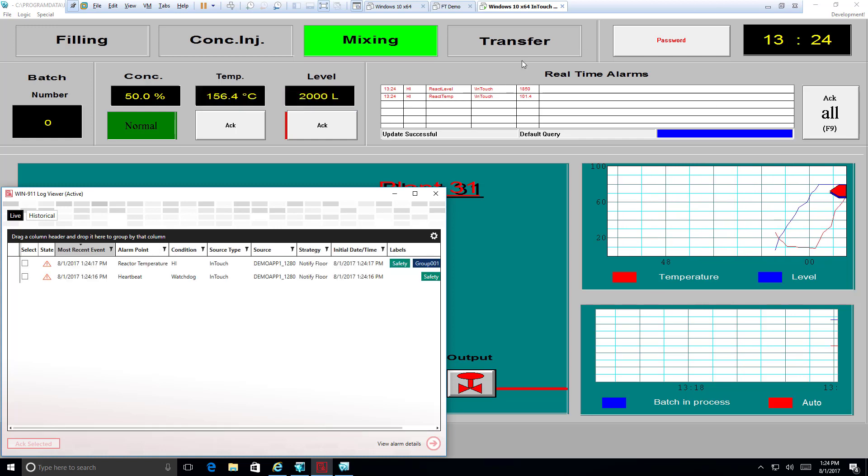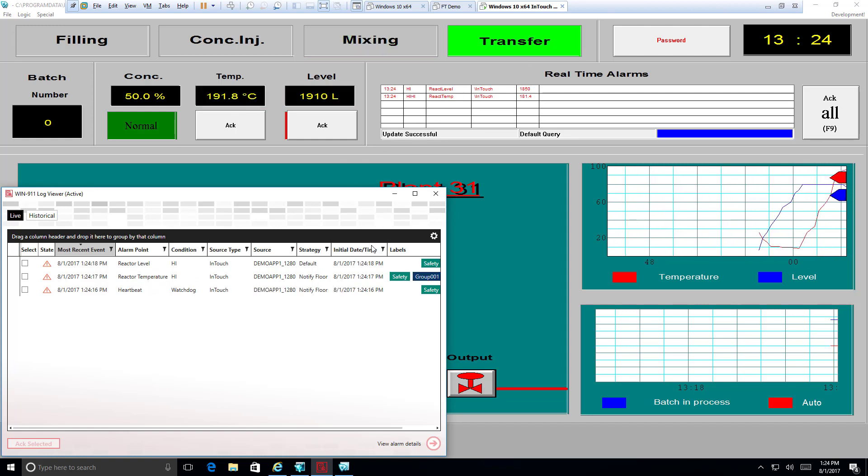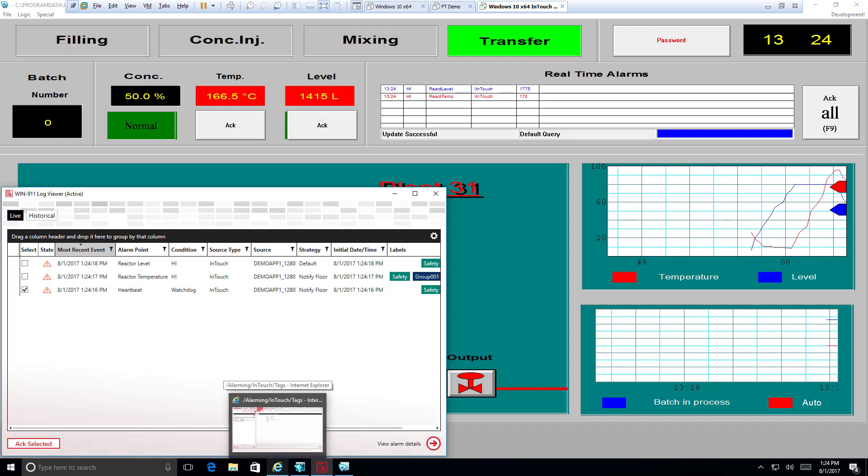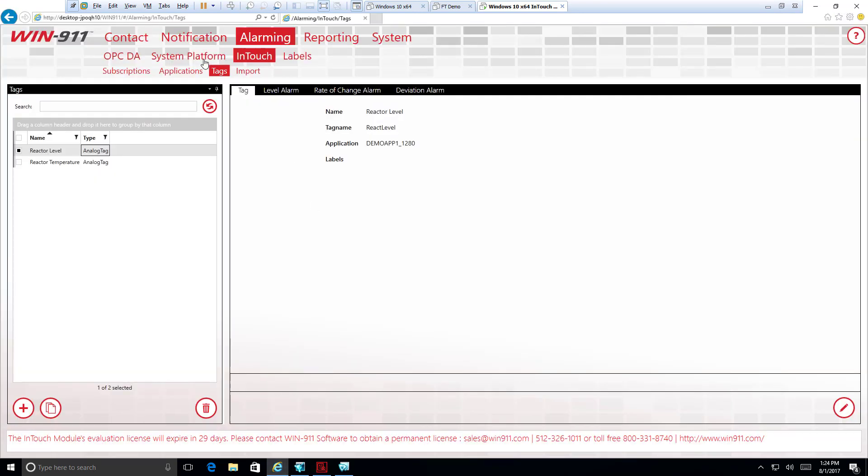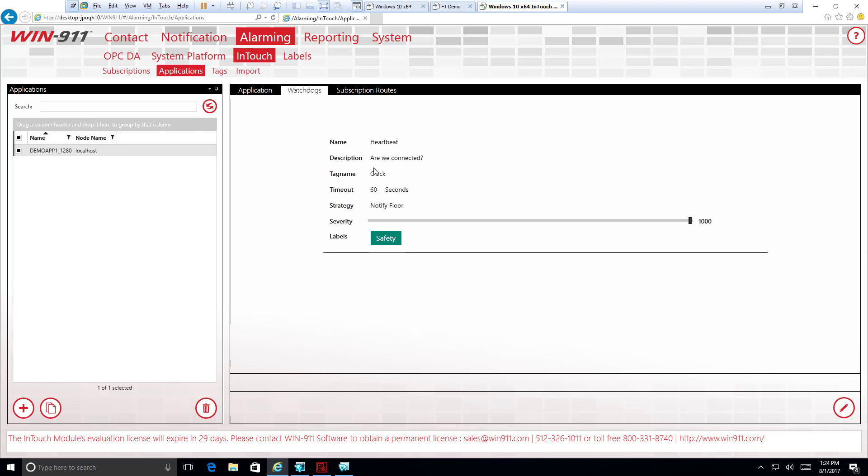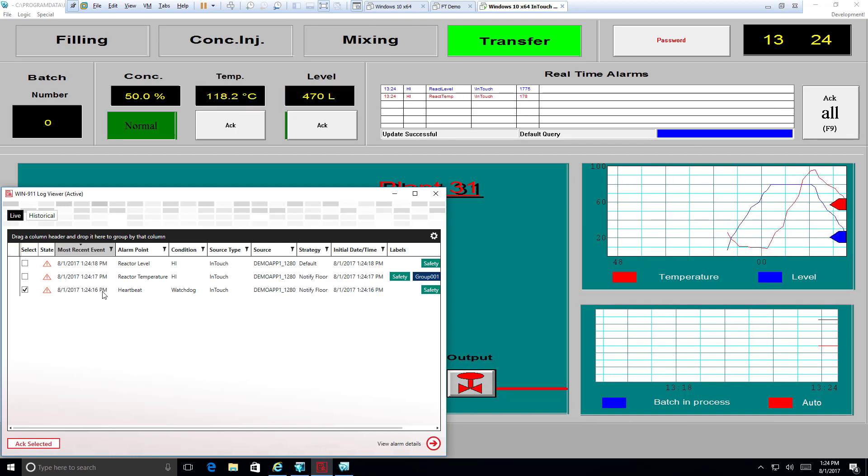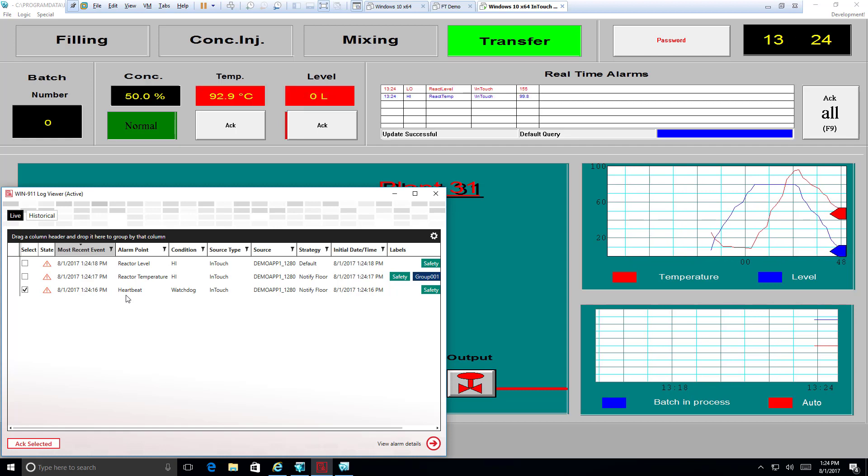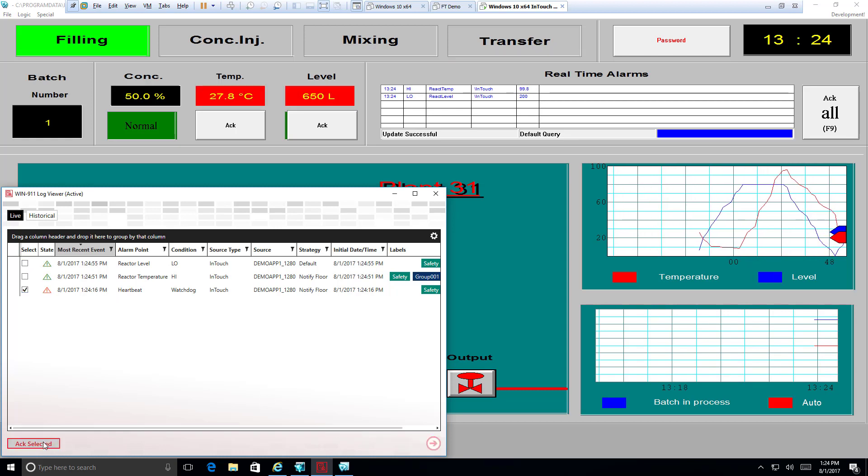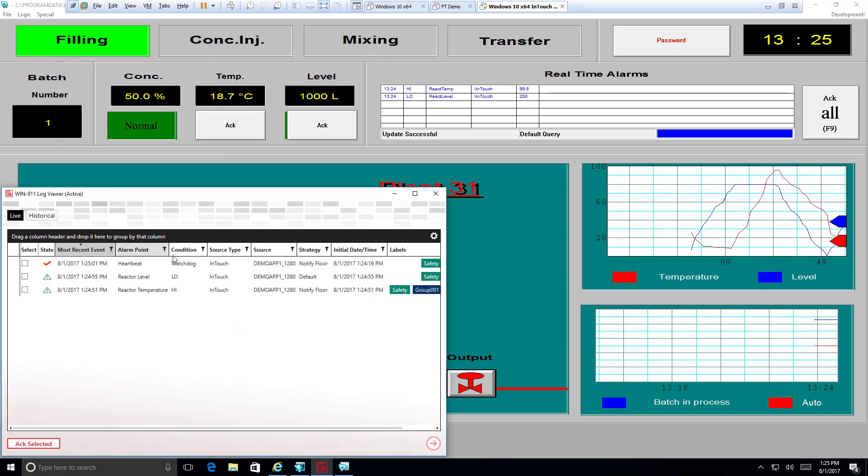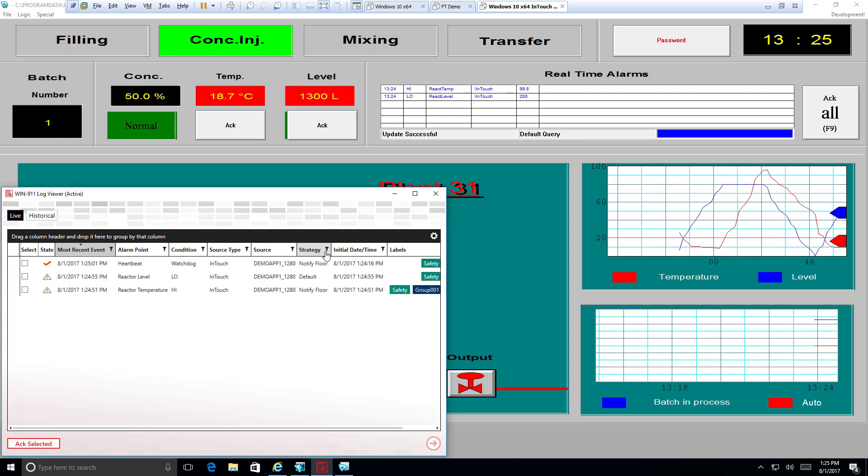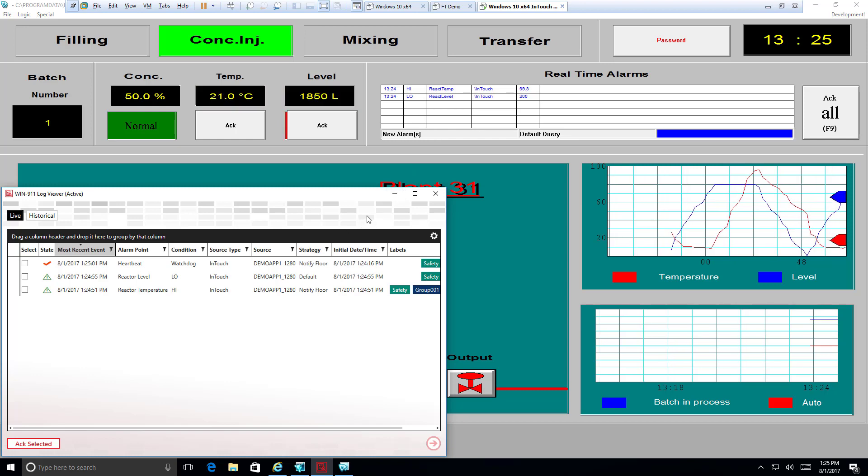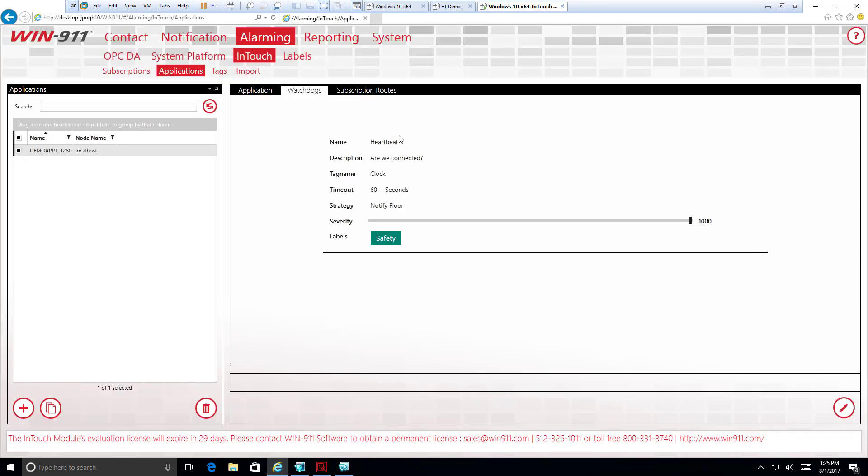Here we go. So actually we saw both our temperature alarm and our level alarm. And we even got our watchdog alarm because we stopped receiving a notification for that watchdog. We can go back if you remember correctly. This is our watchdog. So this is because of course there was no alarm called clock as I told you earlier. So it waited 60 seconds and said hey I'm not getting an alarm from anything called clock. There must be a connectivity issue. So you do want to make sure this watchdog is set up correctly. We can ack from our log viewer. No need for a comment. And that watchdog will be quite noisy here in the future. But that shows that our in-touch application is set up correctly. We have everything working well. And that will complete our tutorial on how to set up the in-touch configuration.